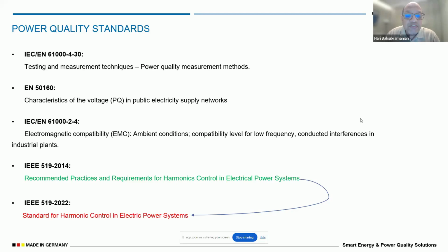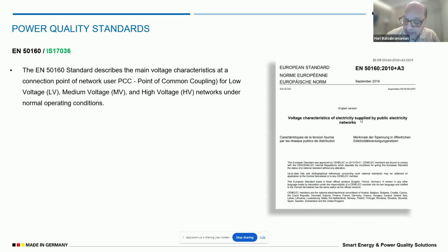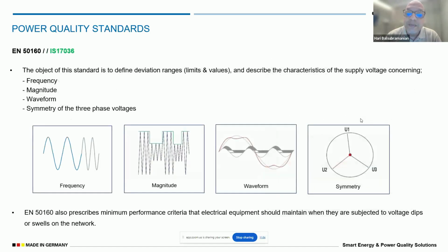So there is a shift in the wording of the standard's title itself, which means it needs to be implemented. As I said, it is no more a choice. It is no more a guideline. It has to be implemented in the consumer premises. So that's how it is done. EN 50160 is, as I said, the mains voltage characteristics, which talks about frequency, magnitude, waveform, and the symmetry of the three-phase voltages. This is what it talks about, and it has its own limits.